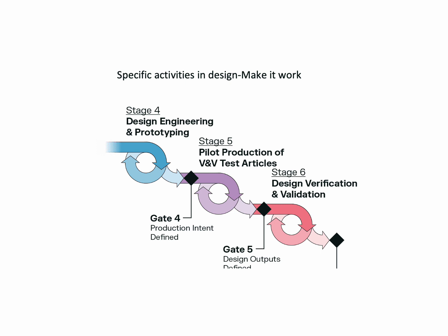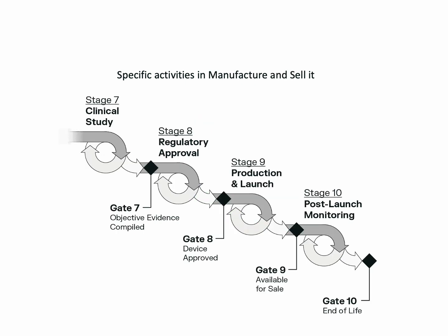This is again what I showed you and talked about from the FDA diagram, where this is an iteration between the input, the process, and the output. And here we are going to validate, because we would like to make sure that each and every function that we are claiming to exist in the medical device is working, and we document it. And then if it applies, we will now go and test the device in humans. We call this, of course, the clinical studies.